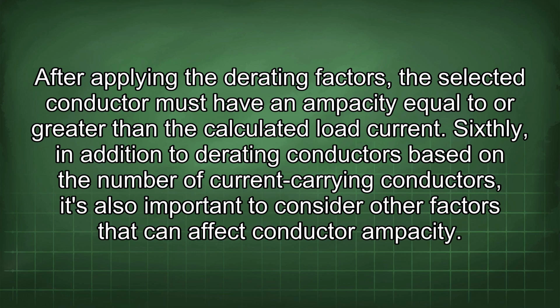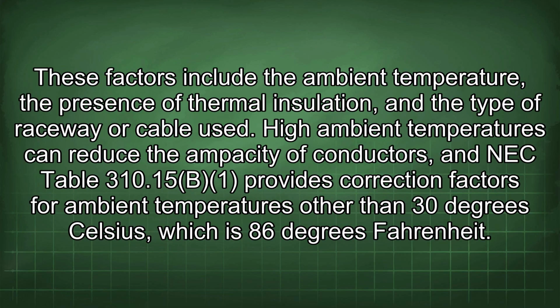Sixthly, in addition to derating conductors based on the number of current-carrying conductors, it's also important to consider other factors that can affect conductor ampacity. These factors include the ambient temperature, the presence of thermal insulation, and the type of raceway or cable used. High ambient temperatures can reduce the ampacity of conductors, and NEC Table 310.15 provides correction factors for ambient temperatures other than 30 degrees Celsius, which is 86 degrees Fahrenheit.